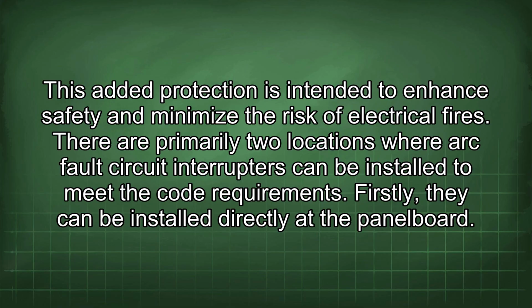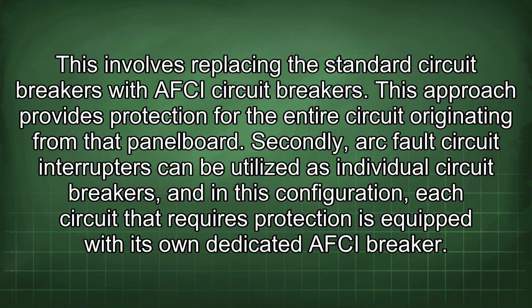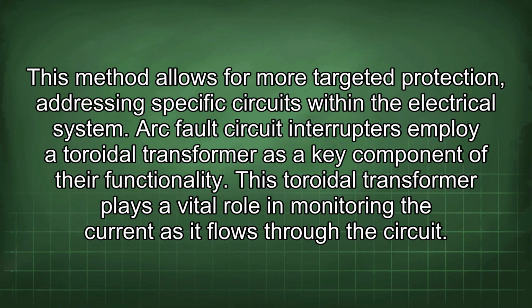There are primarily two locations where arc fault circuit interrupters can be installed to meet the code requirement. Firstly, they can be installed directly at the panel board. This involves replacing the standard circuit breakers with AFCI circuit breakers. This approach provides protection for the entire circuit originating from that panel board. Secondly, arc fault circuit interrupters can be utilized as individual circuit breakers, and in this configuration, each circuit that requires protection is equipped with its own dedicated AFCI breaker. This method allows for more targeted protection, addressing specific circuits within the electrical system.